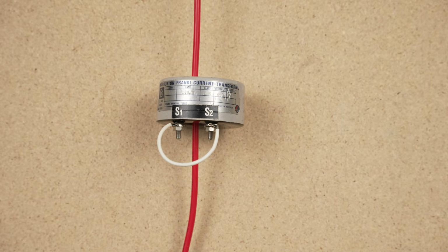Whenever an ammeter needs to be disconnected from the secondary winding, the output must be shorted to maintain loading and prevent a dangerous voltage buildup across the open output terminals. CTs are common items in the electrical industry and are routinely used in metering applications above 100 amps. Which one of your personal electrical meters contains a current transformer?